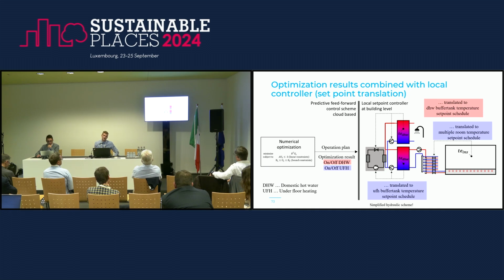We are just translating the set points from the numerical optimization, which are more or less on-off values for the different systems, into adapted set point schedules for the 2-point controllers active in the system. So on one hand we have the advantage of an optimized strategy, but on the other hand we have the robustness of the local controller, and we still gain thermal comfort inside the building.